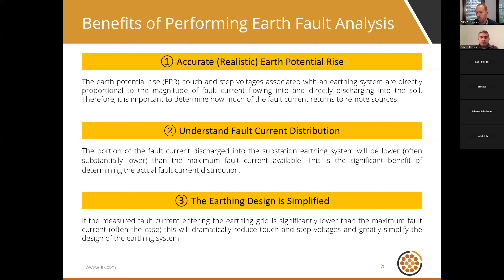The third benefit is that the earthing design is simplified. When designing the earthing system, if we only need to deal with a portion — very often a small portion — of the prospective earth fault current, this can dramatically reduce touch and step voltages and greatly simplify the design, making it simpler and more economical.